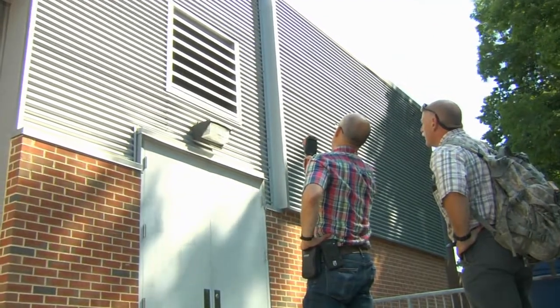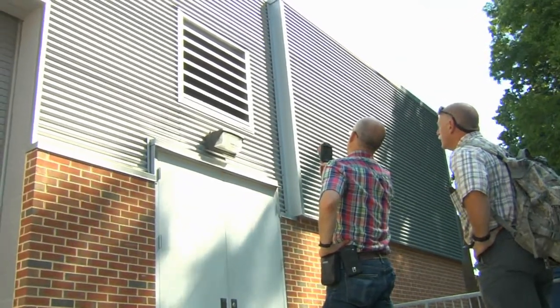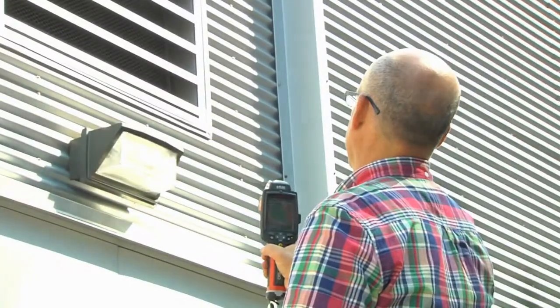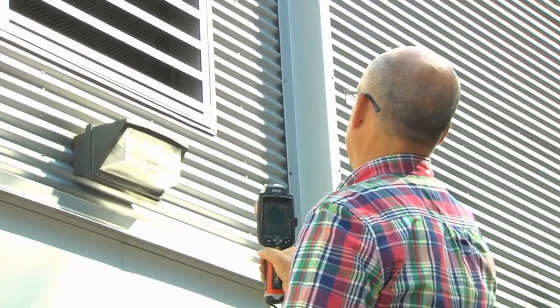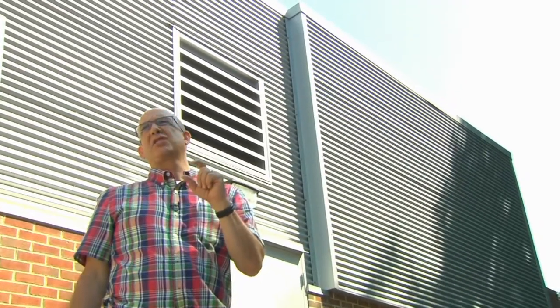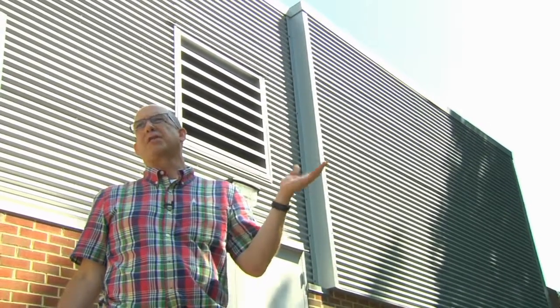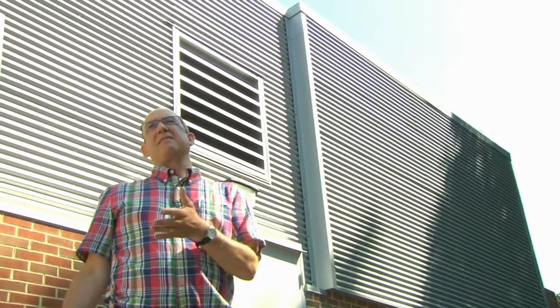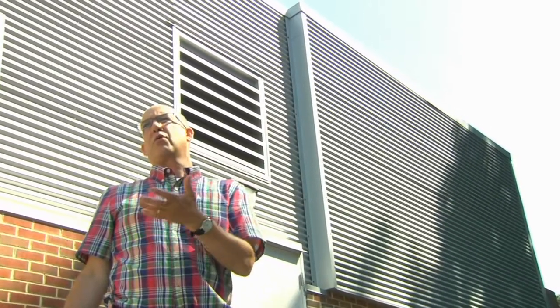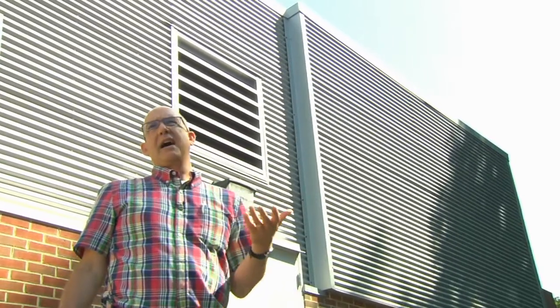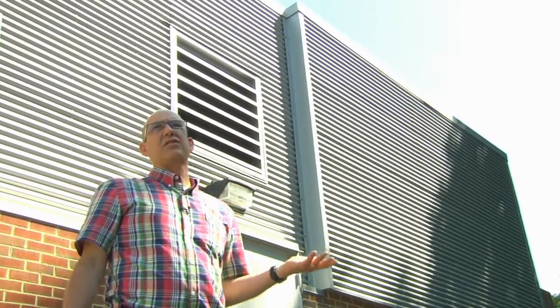The question is, can it be raised? Can it operate at 90, 95? I don't know. That might be something to look at. Again, we're talking small changes in set points. 85 is a good number. Someone picked it. You might have to look at what the electrical equipment's rated for. I would recommend doing that as an exercise anyway.